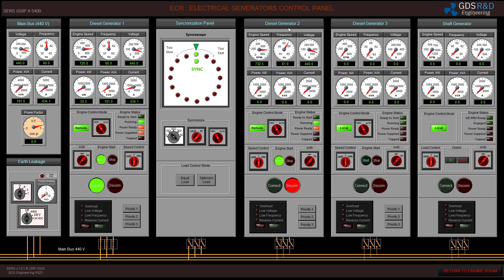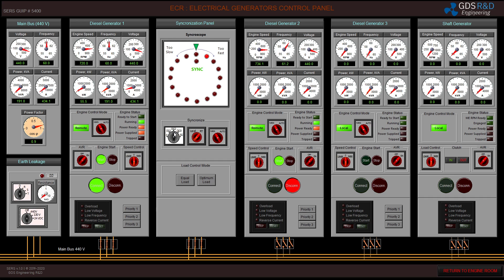Diesel generator number two is running and the power is ready. I will switch the synchronizer control to diesel generator number two. As you can see, the synchroscope indicates the engine speed — and therefore the frequency — is too high. I have to lower the frequency and stabilize at 60 Hz. I'm going to adjust the engine speed.